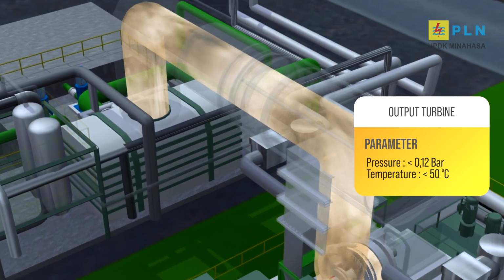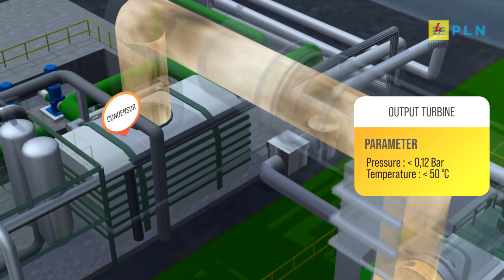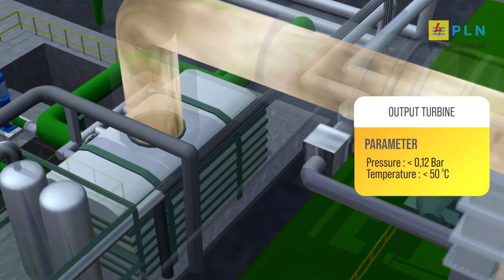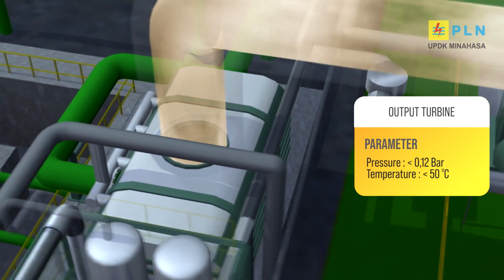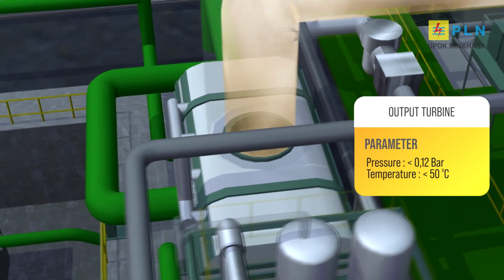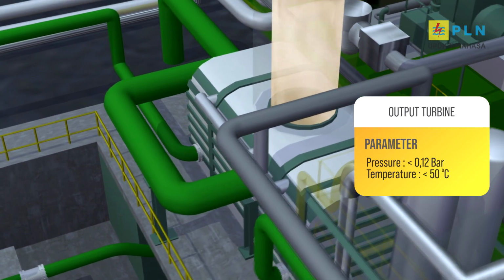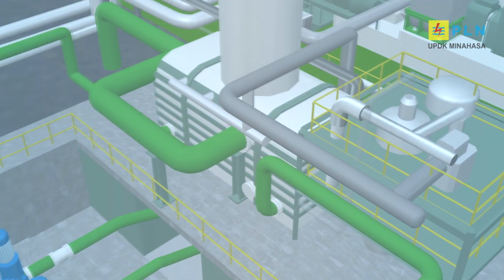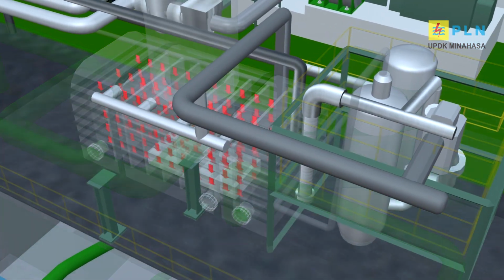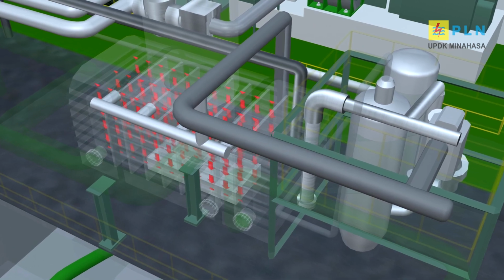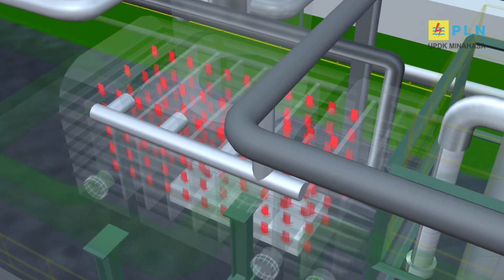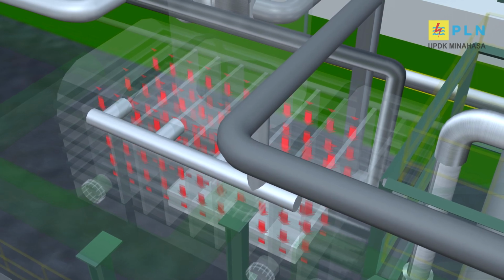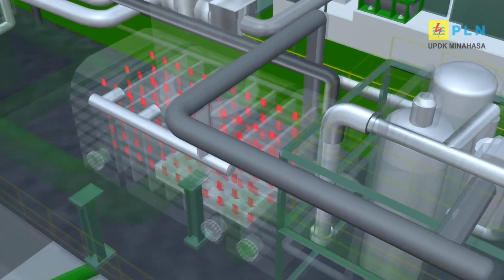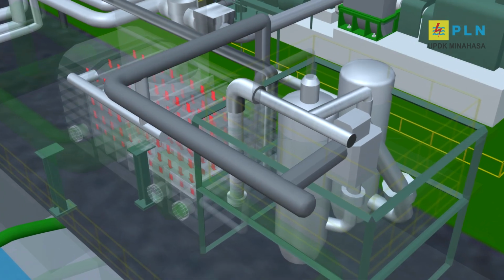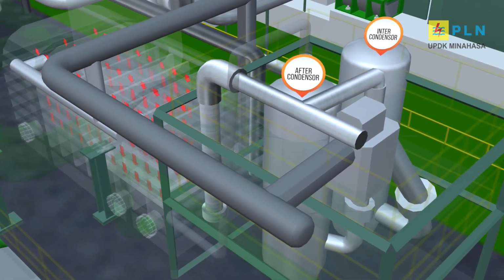The steam which is used to rotate the turbine then enters the condenser to convert steam into water through a condensation process in the condenser with the direct contact type. At this stage, there is a direct cooling process, namely, the turbine output steam is cooled using the main cooling system. During the condensation process, the condenser operates on a vacuum with a pressure of 0.120 bar absolute at full load of 20 megawatts. The vacuum condition in the condenser is assisted by the gas removal system.